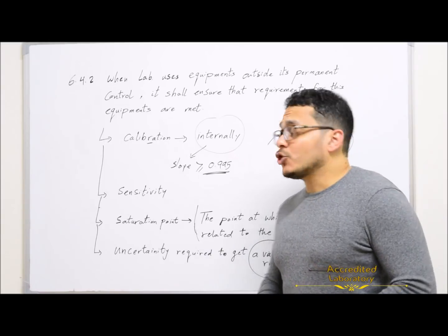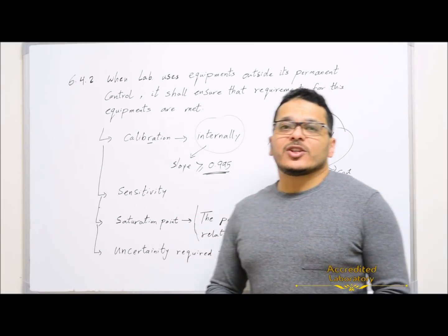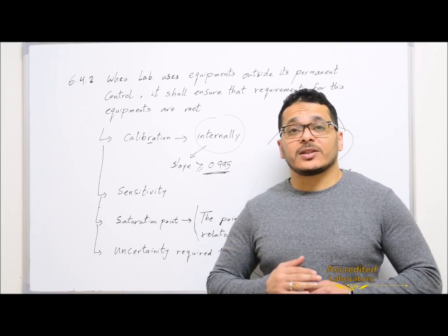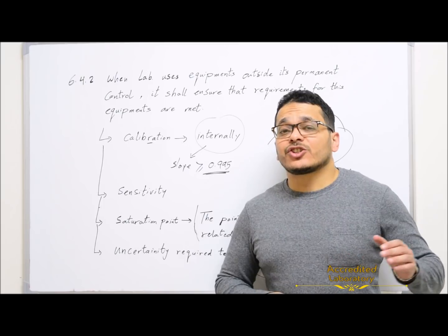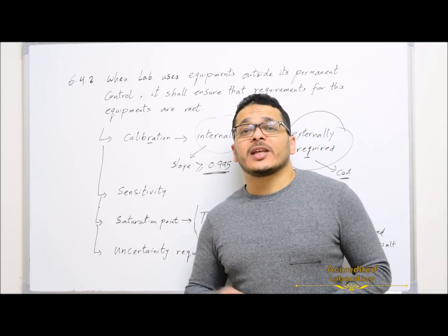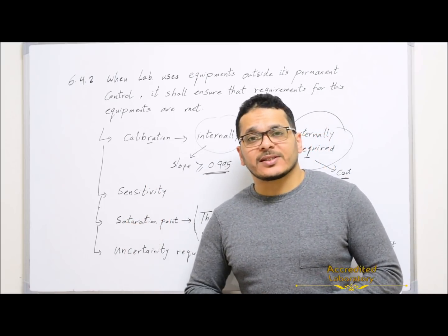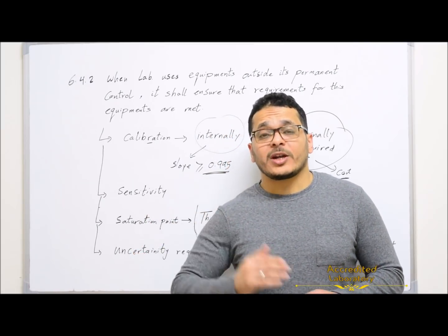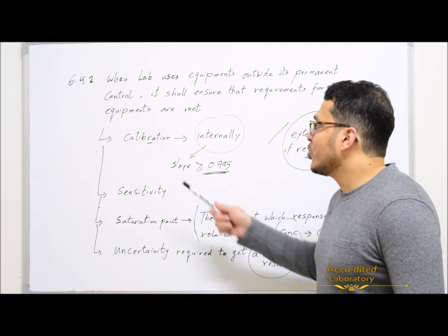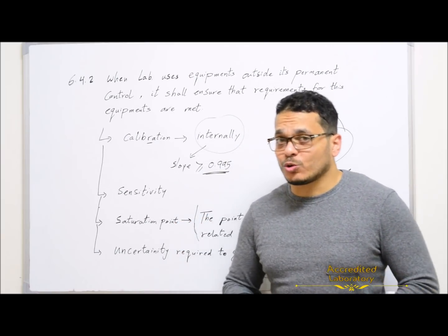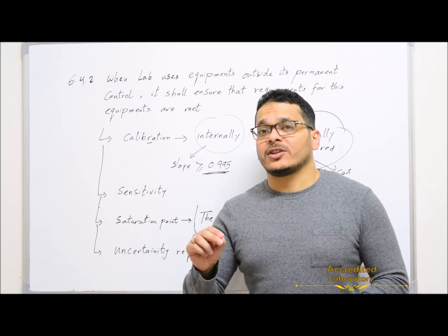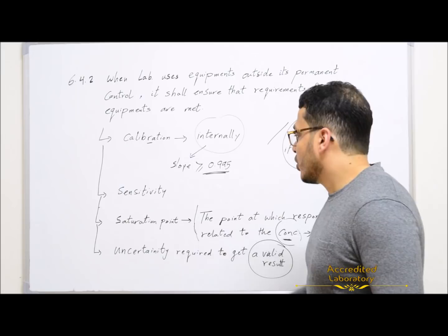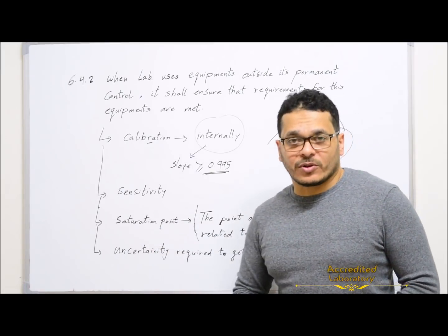Also, the lab shall ensure the sensitivity of the instrument. What is the lowest concentration that can be detected by this instrument, and the concentration that can be quantified by this instrument and get accurate and reliable results? And if this concentration fits this method or your purpose or not. The lab shall ensure the highest concentration required to be analyzed by this instrument. So you will ensure the saturation point for this instrument.